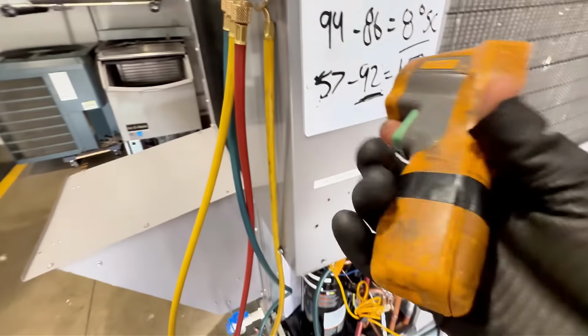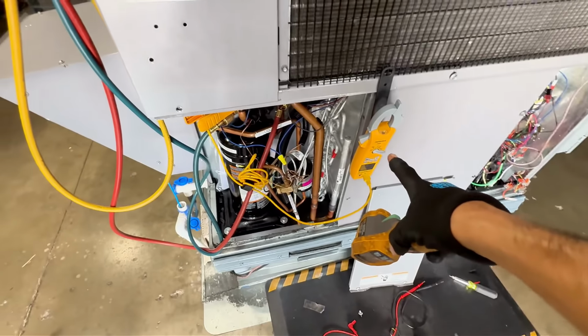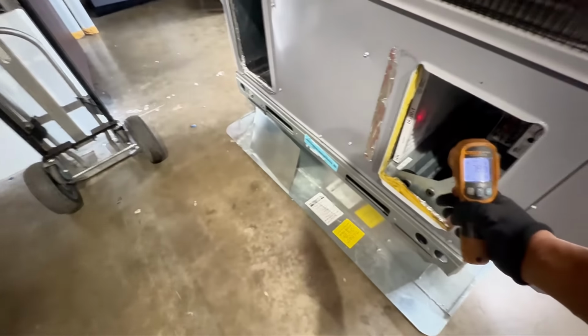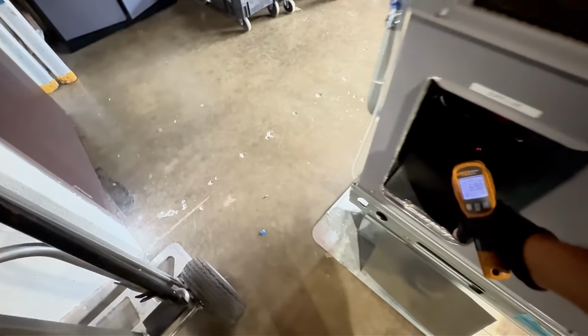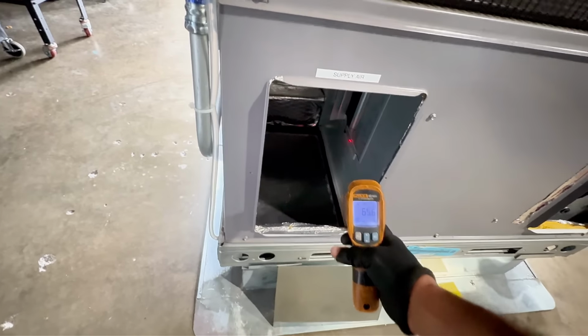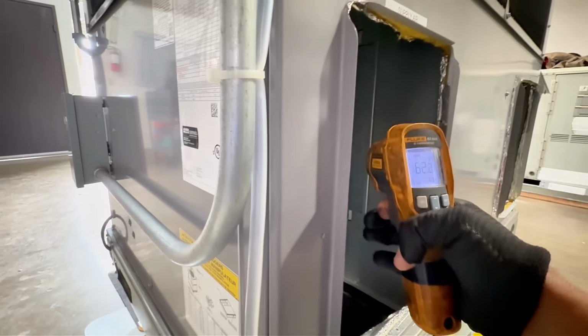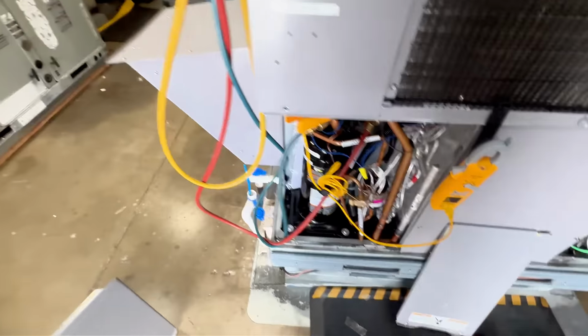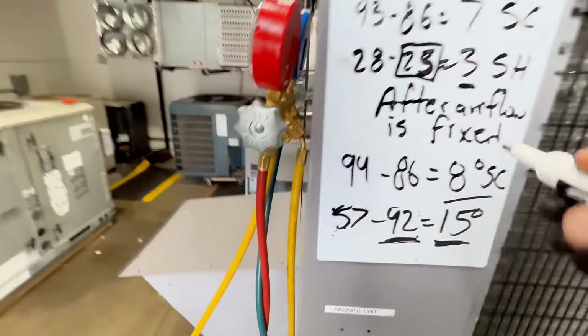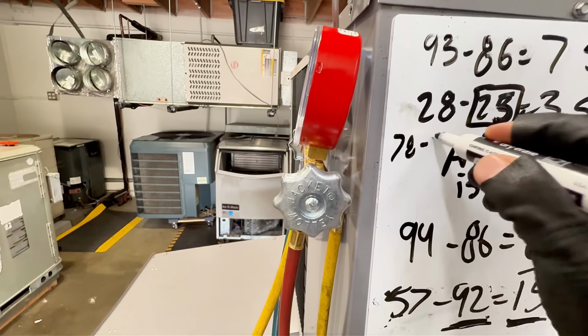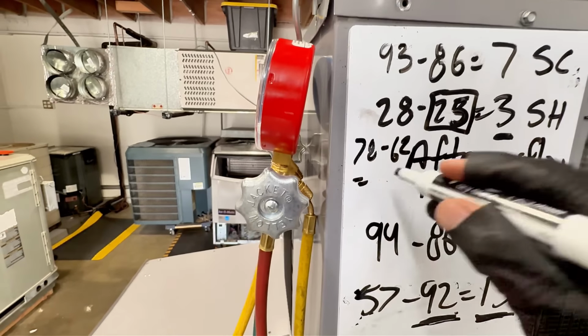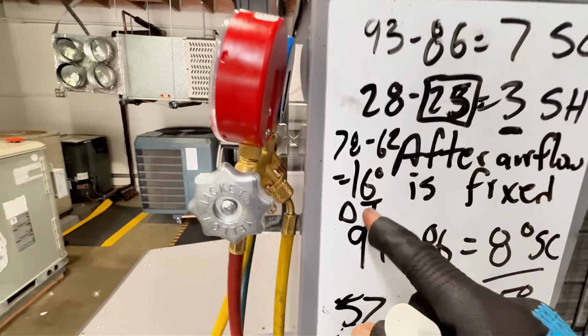Another little test, and you don't need to get a temperature gun. I've had this for years, but this one comes with a little thermocouple where you can get the temperature, but you can also get your delta T. What is it right here? We have 78, and technically it's better to get probes, because probes are more accurate, but it's just to give you an example. So 78 and 62. So my delta T, 78 minus 62. What is that? 16 degrees, so my delta T is 16 degrees.